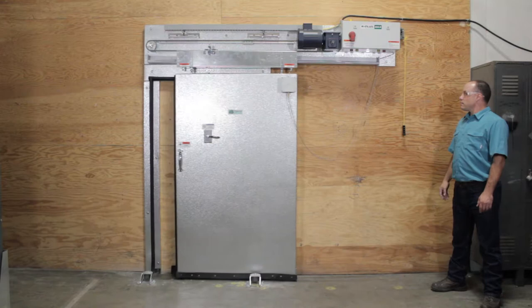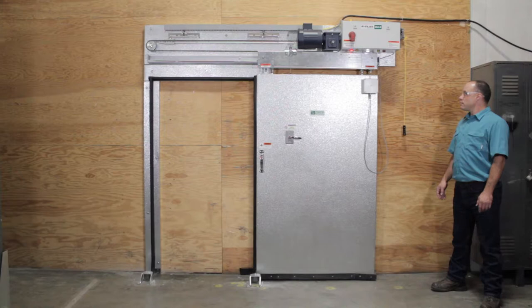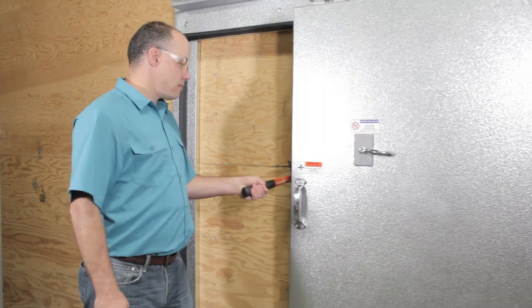Now turn the power back on at the controller and test cycle the door through its complete operation. Retest the safety edge for proper operation and adjust as required. You have completed this adjustment if the door successfully stops and returns to the safe position when tested.